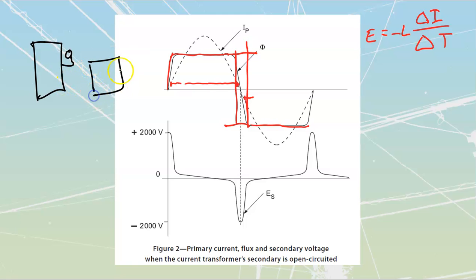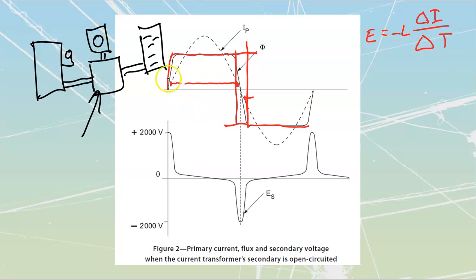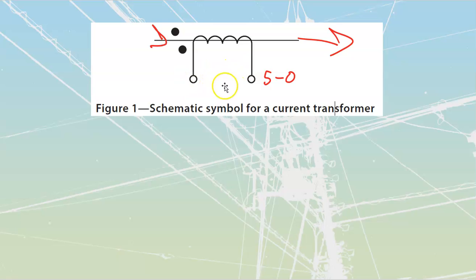We'll draw that in over there, and then we'll draw this in over here. This is going to be a distribution, electrical panel, could be splitters and switches, whatever it's going to be. This is going to be my main incoming switch, and this is going to be something referred to as our metering cabinet, where we store all of the CTs. Over top of that metering cabinet is going to be a little meter base. Now, the problem is that that little meter base is only tapping off of these windings over here. It's not actually interrupting the main current.